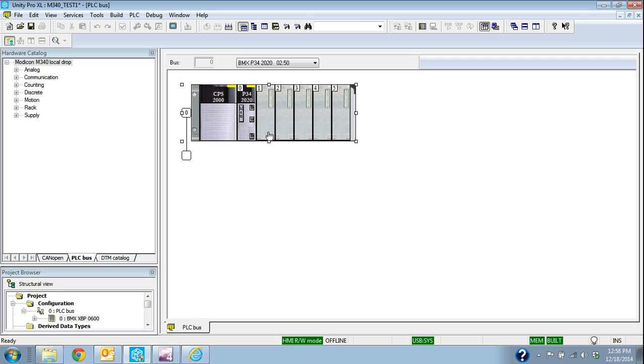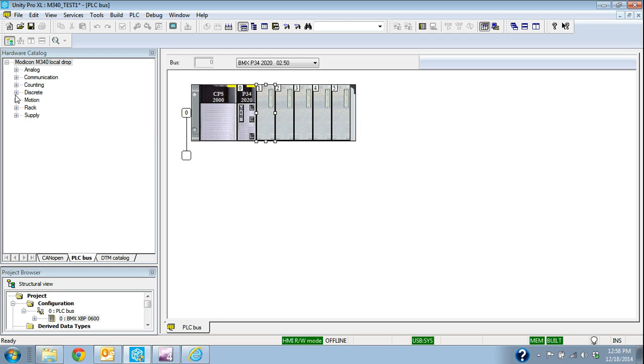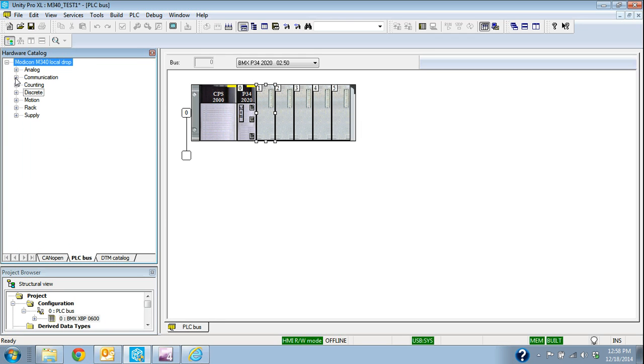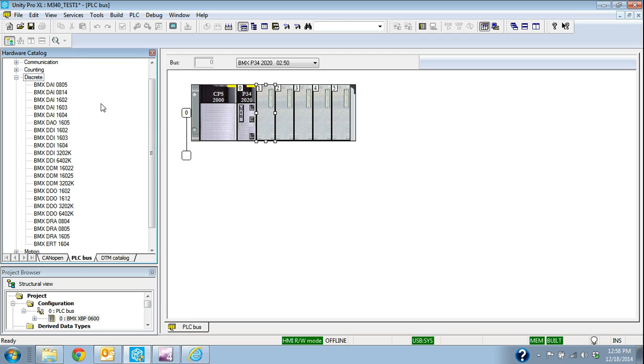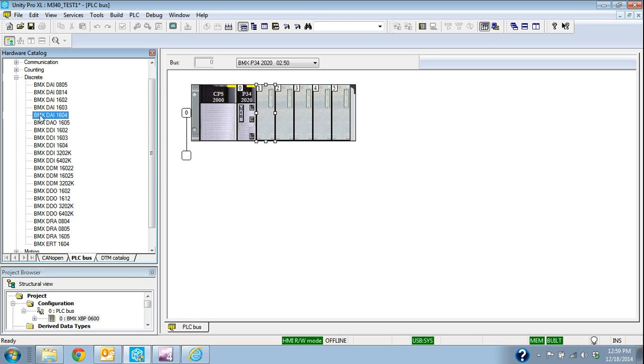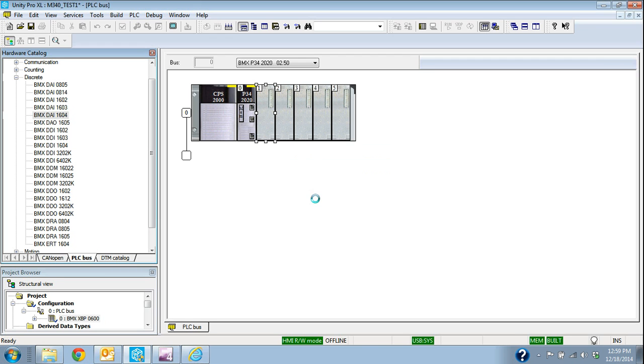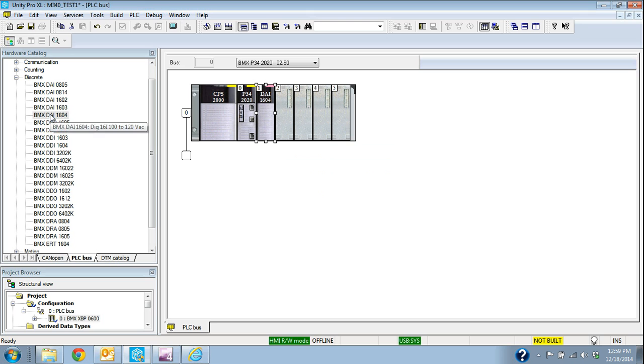If I was to go to slot 1 and say we're going to put a digital input card in slot 1 or discrete, I go over to discrete and I select my drop-down here. If we're going to use, let's say, a DAI 1604, which is 120 volt AC, well, then if I hold the mouse button down, I can drag it over, and it'll put the card in there for me. That's one way that I can do it.